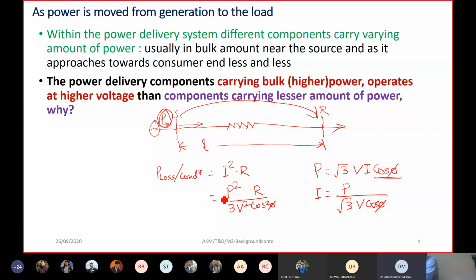Then this is loss per conductor. In the three-phase line, we have 3 lines, so the total P loss in the line is 3 times P square R upon 3 V square cos square phi. That means this 3 gets cancelled.